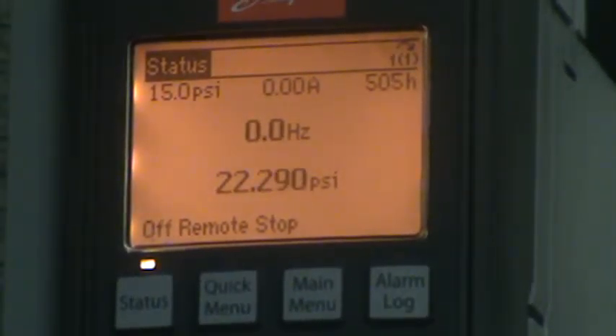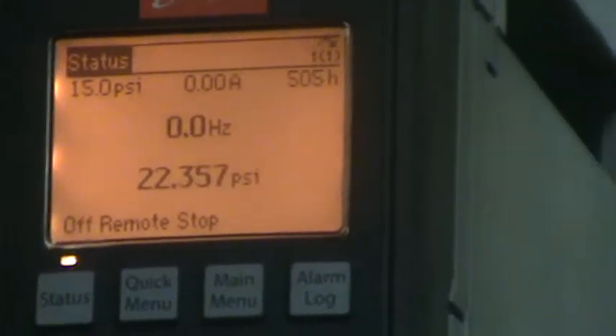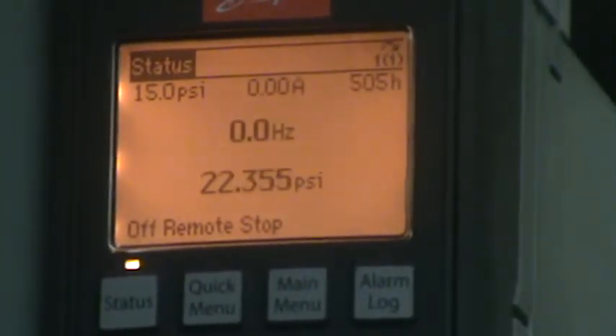Any of your main ones like that, like phase loss and ground fault and short circuit, stuff like that, have to be manually reset. You have to turn the drive off and on again. A lot of the smaller ones, like the current ones, stuff like that, you can simply just hit the reset button and it'll start back up again. I can't remember exactly every single one that has to have a power cycle. If you hit the reset button and it doesn't cycle power, just turn it off, turn it back on.